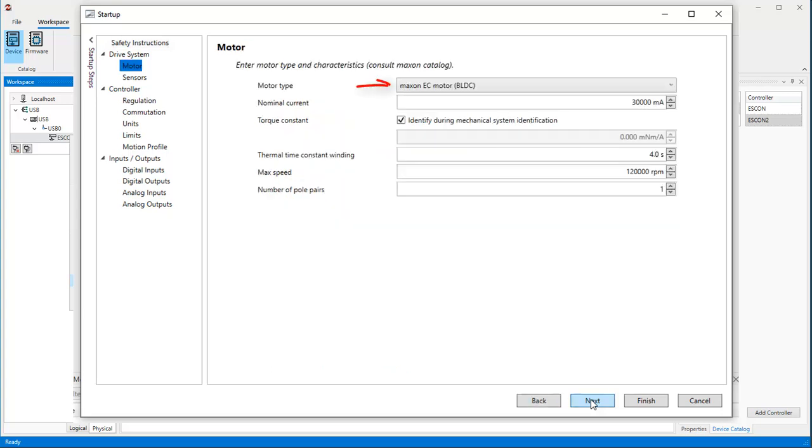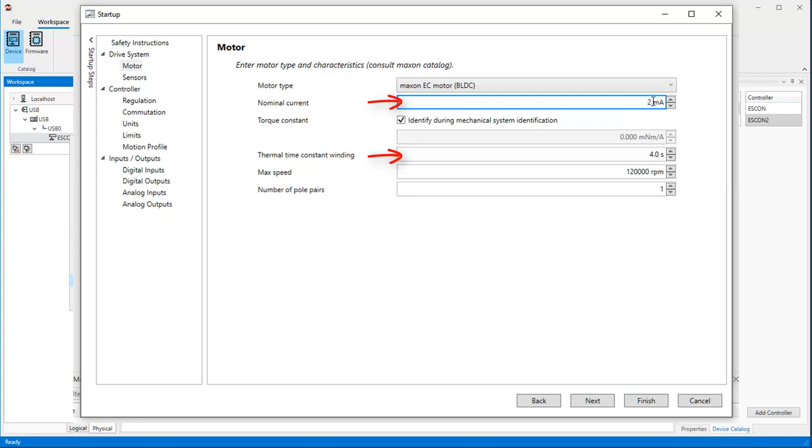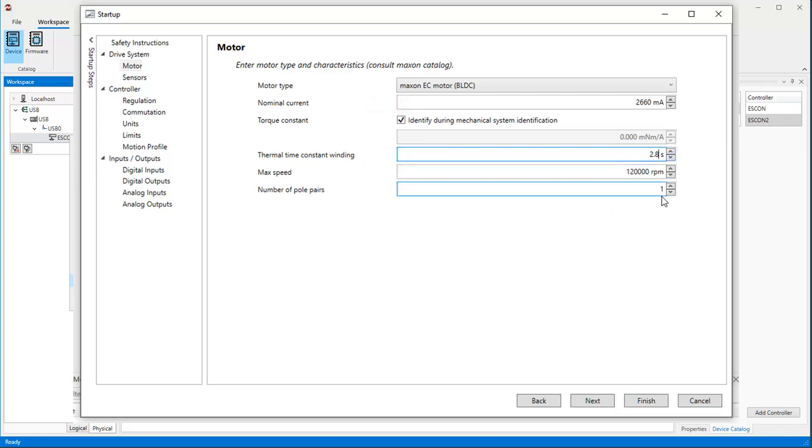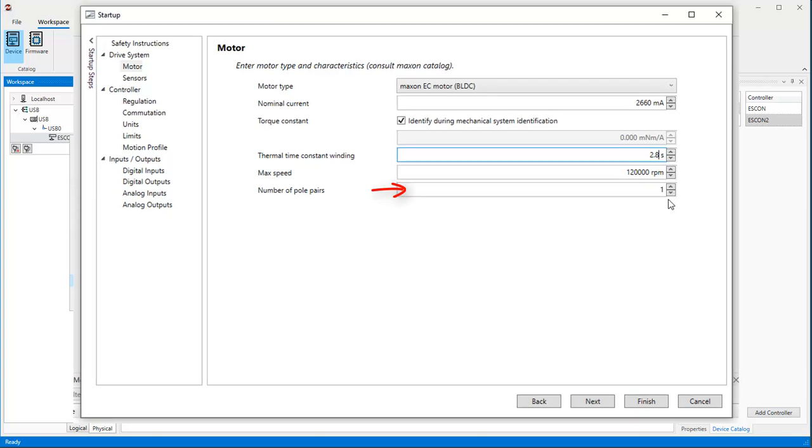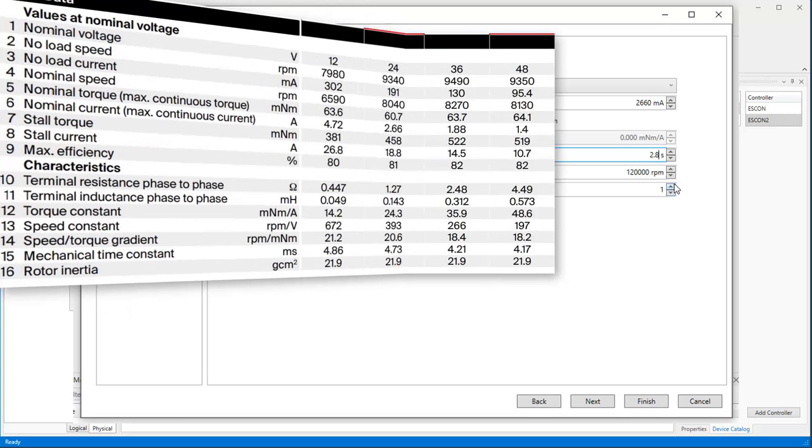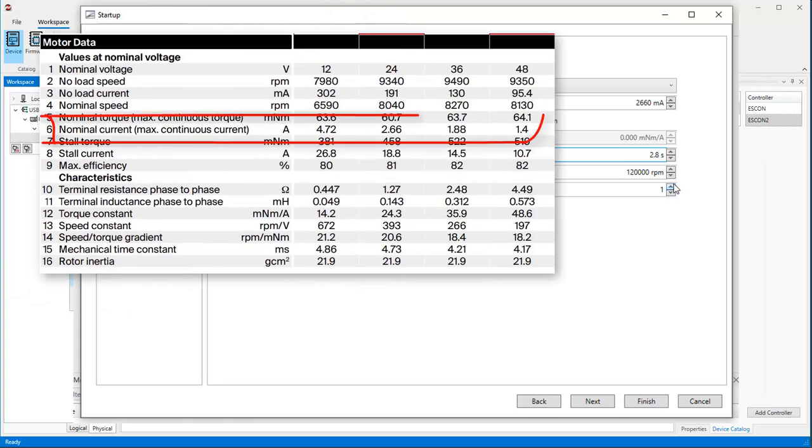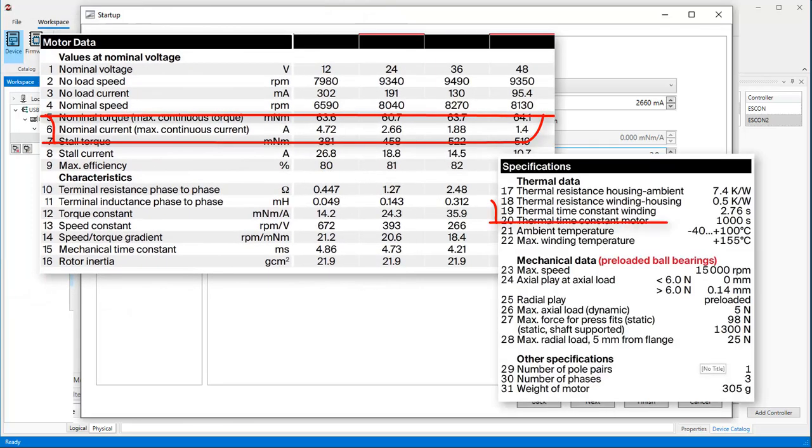For a brushless motor select Maxon EC motor. Specify the nominal current and the thermal time constant of the winding of the motor. These two parameters are required to protect the motor from overheating. In my case, the nominal current is 2660 mA and the thermal time constant is 2.8 seconds. Define also the number of pole pairs of the motor, which is 1 in my motor. You can find all these values in the specification of your motor.